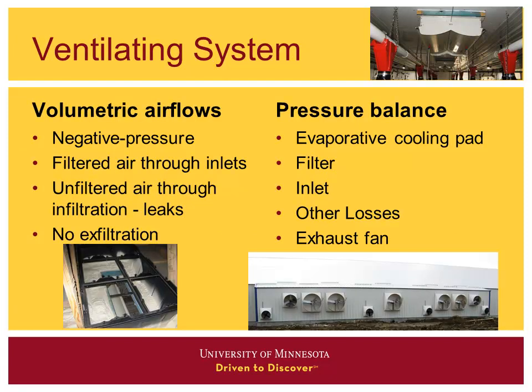The ventilation system had negative pressure with filters on the inlets. Unfiltered air comes through infiltration through the leaks. There's no exfiltration, so what came in through the inlets plus what came in through the leaks equaled what went out the fan — that's the mass balance. The other balance an engineer uses is a pressure balance: the fan generates a pressure that must equal the pressure lost going through the cooling pads, filters, inlets, and any other ducts.